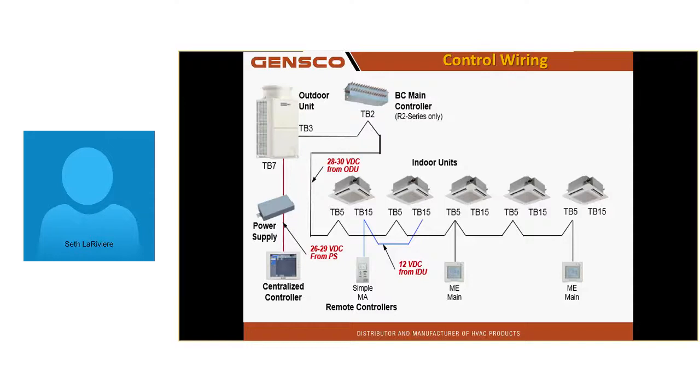And there's a backdoor access I'm not going to tell you, in case I ever have to get in it after you've changed it and lost the access code. And they don't give out the backdoor access code anymore because this thermostat has a fatal flaw. If this is installed in a condo situation or a hotel type situation, and someone has intimate knowledge of how these things work, I can go into that ME stat and take over every other unit in the building.